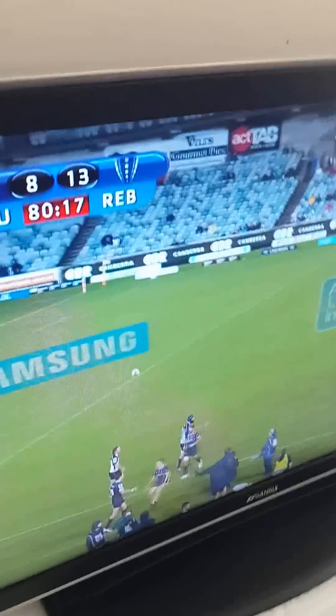We've still got the DSTV. We've still got whoever's losing here. And it tells us that we're running on auxiliary power, and we're still getting 226, 227 volts. I'm now going to plug this in. The fan will keep running until the battery gets back up to whatever I've taken out of it. And it should any minute say we're back — we're now on live mode again. So that's how it works.